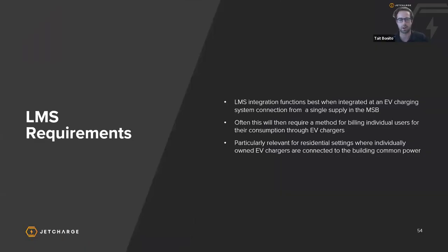Firstly, linking this to the LMS requirements: typically when we install a load management system, the most suitable method of obtaining a supply and connection for the EV charging system and the load management system is via one central connection point in the MSB. That means when it comes to metering, there's only going to be one meter. So if it's a residential apartment like JSL's example, the DBEV or the busway will be connected from the metered section, the common power of the building. That means there's only one entity that pays the energy consumption for all the EV charging energy usage. So we need some method to recoup those costs for the energy account holder and make sure the individual EV charger owner is paying for the energy consumed through their charger.